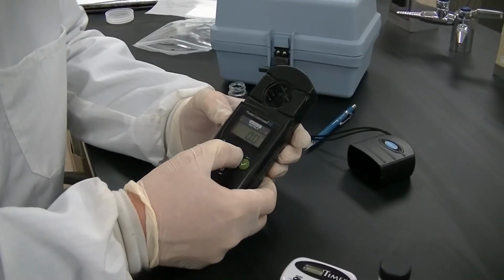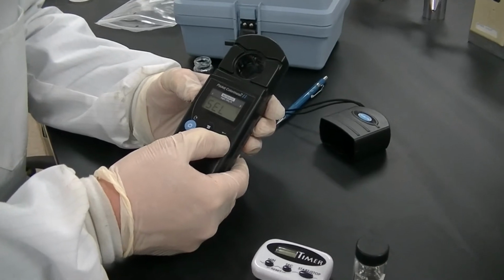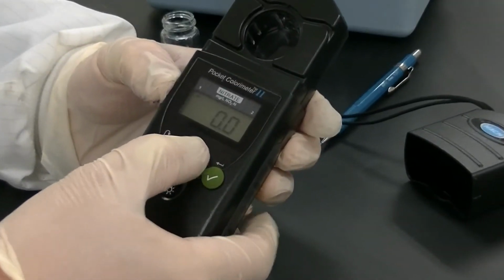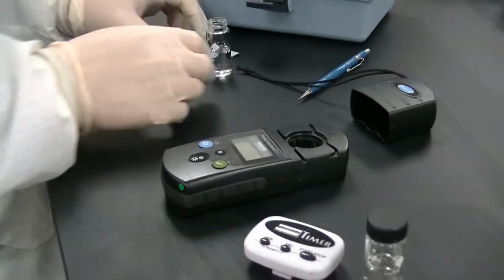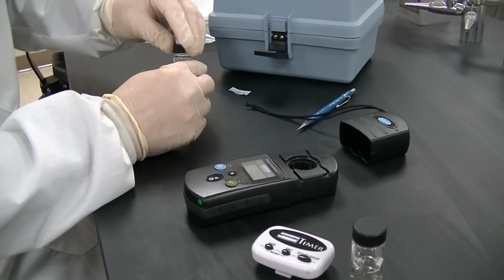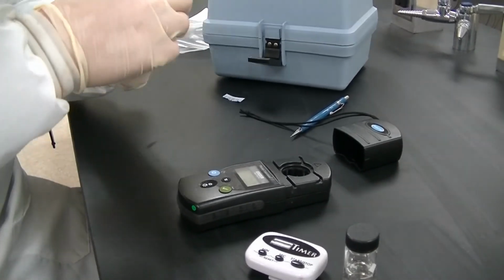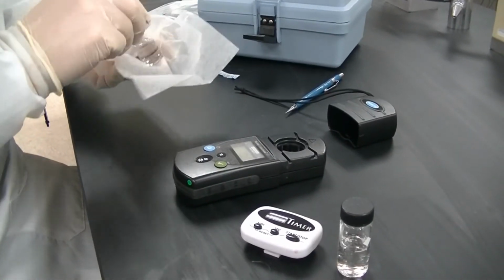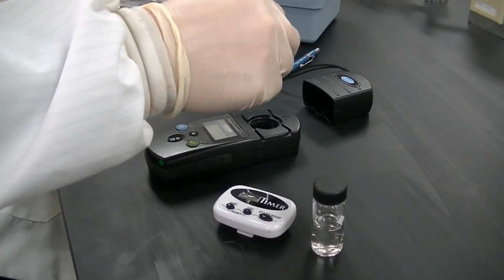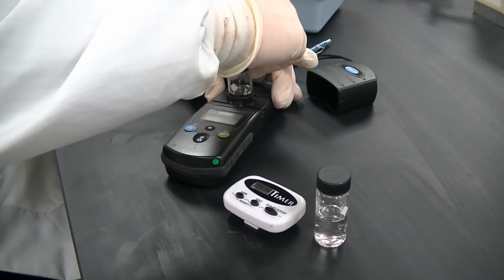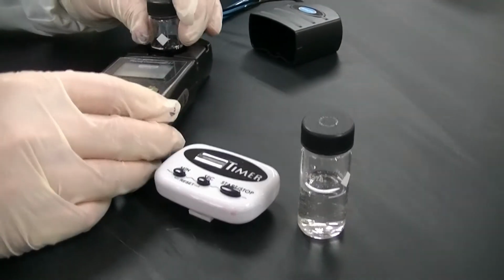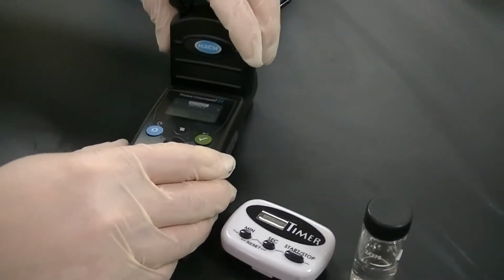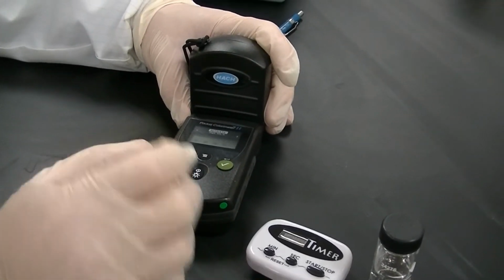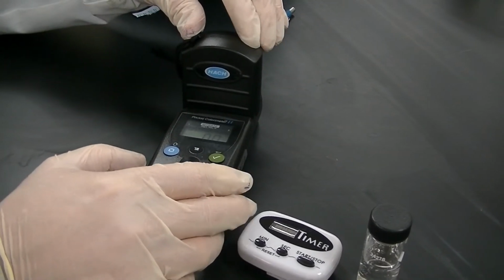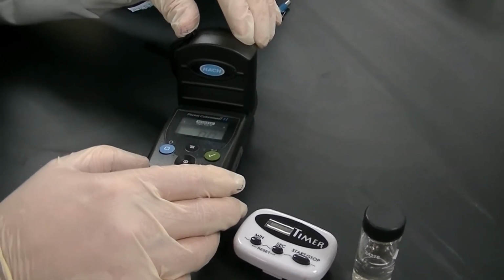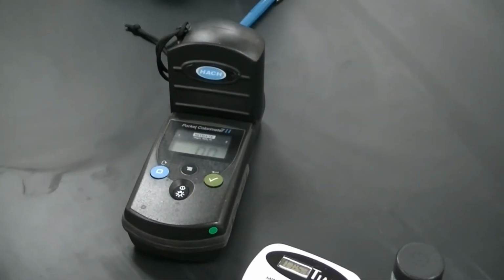We're on channel 2. We want to set it back to channel 1. So we can do that in this fashion here. You see it goes back to channel 1. Okay. So we'll prepare our blank. I'm going to wipe it down. I actually have some lens paper here. Wipe it down, and the little triangle goes in the front. We just enter that in there, put the top on, and then we'll hit the 0, and that will subtract out any of the background color in that sample. Okay, and now we'll wait.